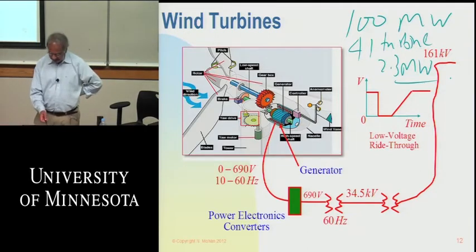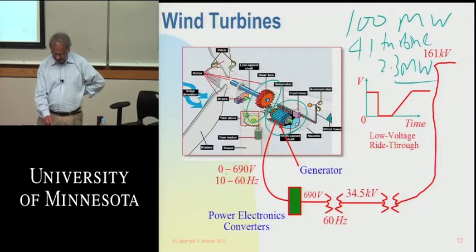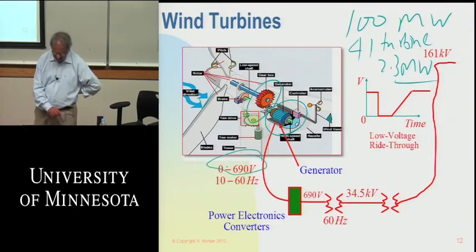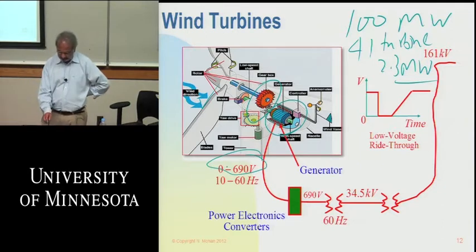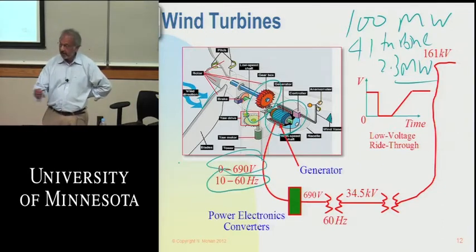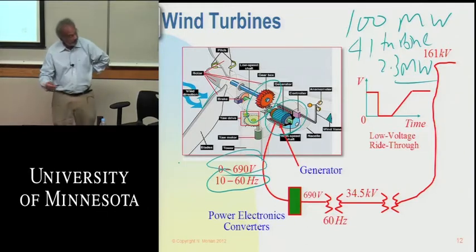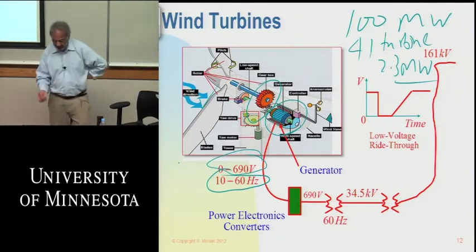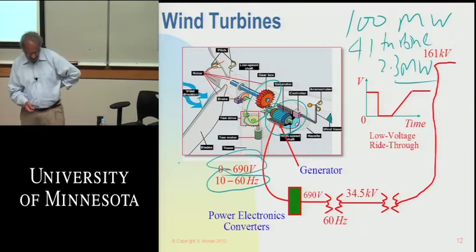If you look at any of these wind farms, you have the turbine, the gearbox, and then a generator at fairly low voltage, in this case up to 690 volts maximum, producing electricity at variable frequency depending on wind speed. The faster it turns, the higher the frequency.